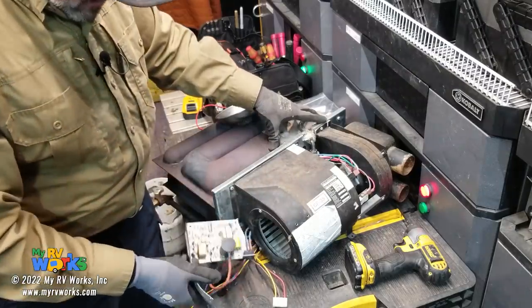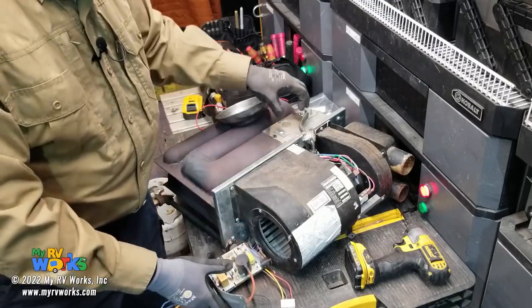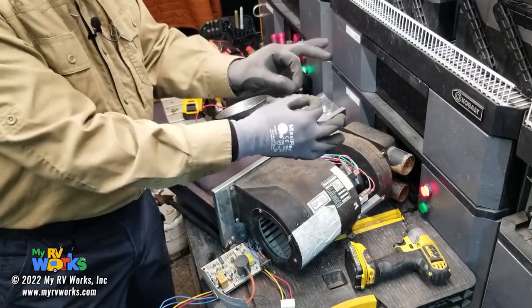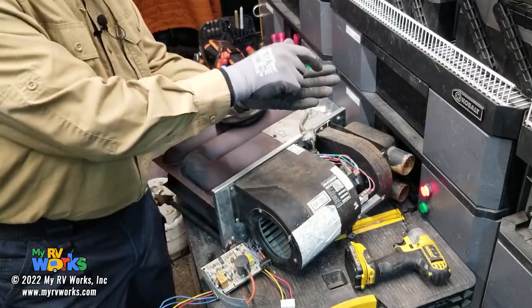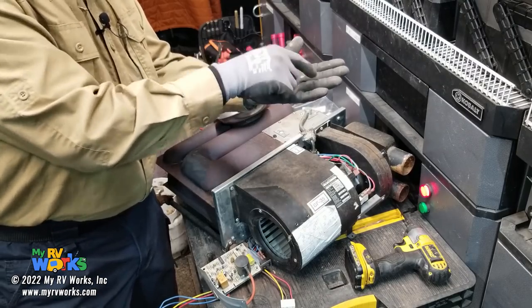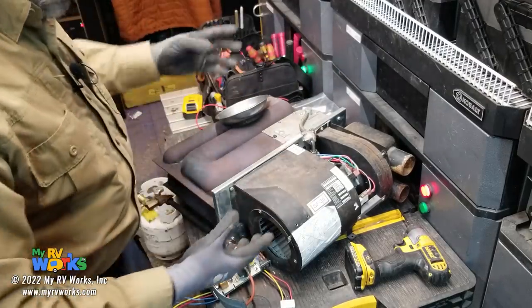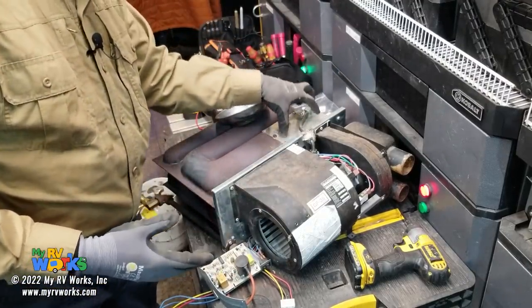So in that instance, it could be the control board. It could be the electrode itself, the wire. It could be the metal in the ceramic housing. It could be the location of the electrode over the burner head, both north, south, east, west, but also the gap up and above. Okay. So from all my experience, my position is it's probably going to be something inside of here.